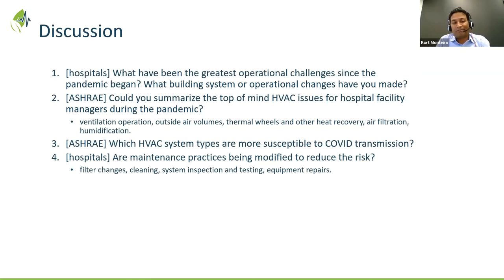Kurt, that differential pressure verification—what does that process look like for a hospital that hasn't gone down that path yet? How do you work your way through the operating suite to make sure you've got that? Is it done through the building automation system, or with handheld devices? In modern hospitals, with every OR having its own differential pressure monitor, that's done through the BAS system. Otherwise, you're usually getting the balancer to work with you to measure the differential pressure between the adjacent spaces.